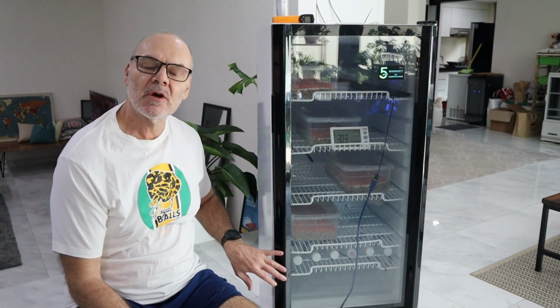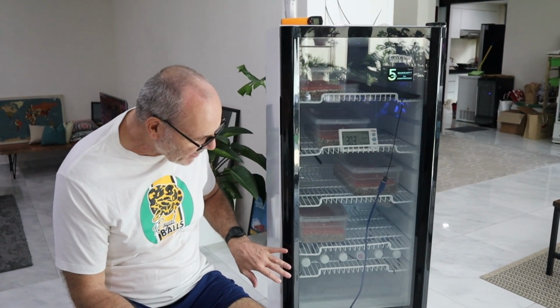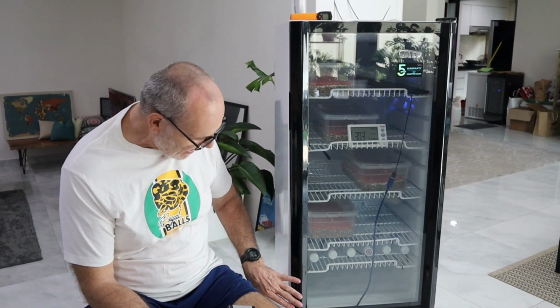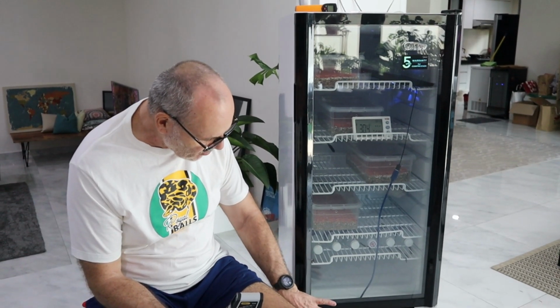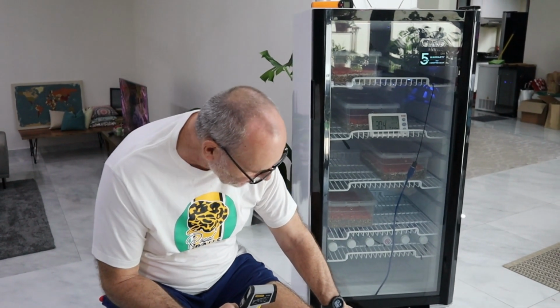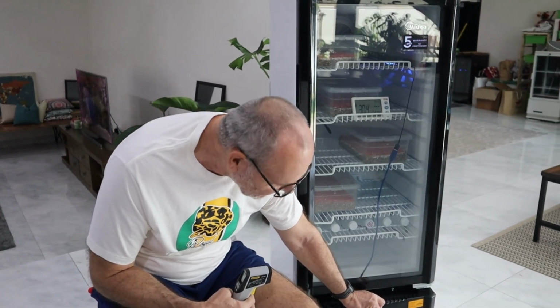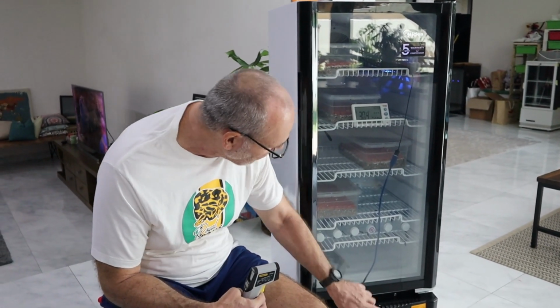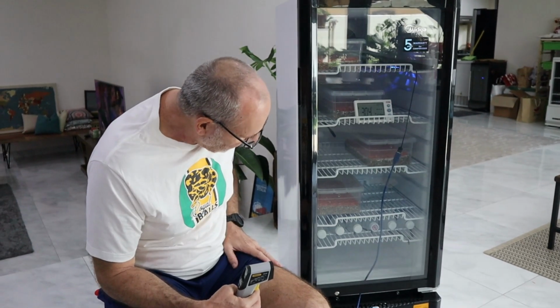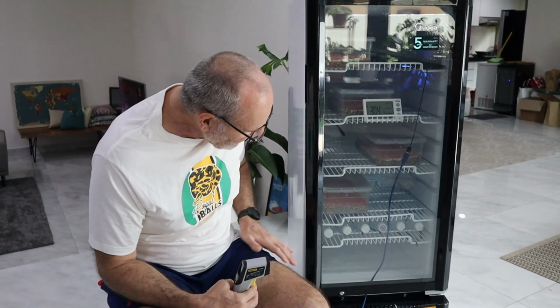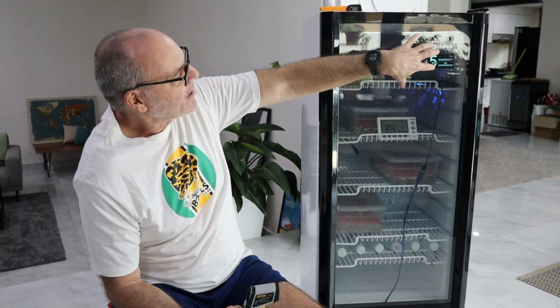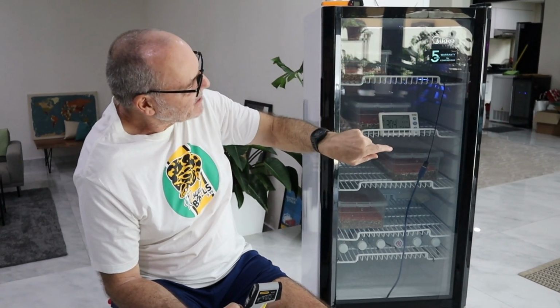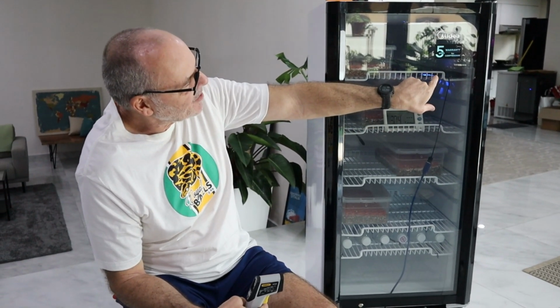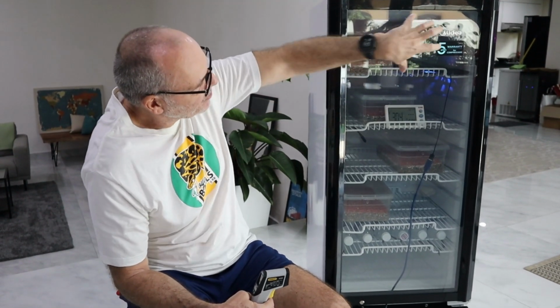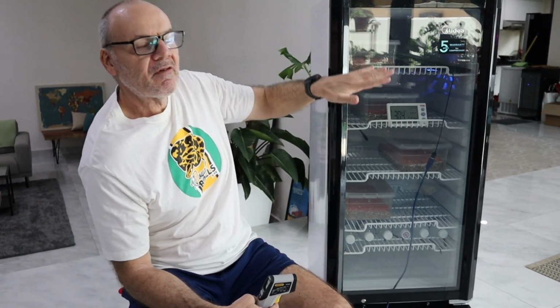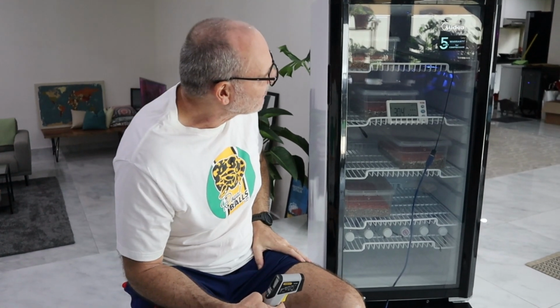But over the last couple of days of playing with this incubator, I've learned a lot about the incubator and the equipment itself. I know that the thermostat is extremely sensitive, and a tiny little change to this dial here makes quite a big difference to the temperature in the incubator. I know that I have a dead space at the top, so I need to have a fan, and the best solution is a fan at the top pointing up just to disrupt this dead space, and then I get a very even temperature throughout the incubator.